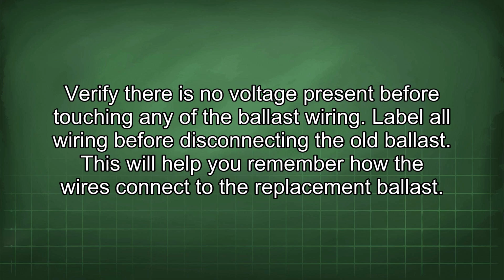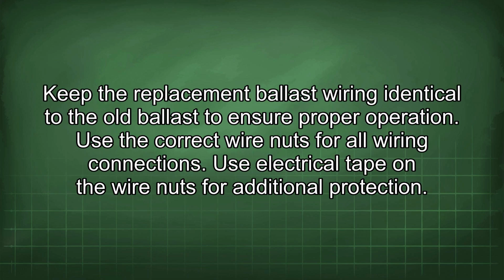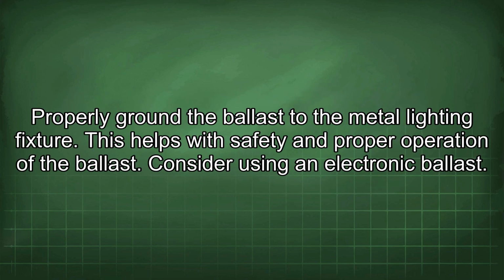Label all wiring before disconnecting the old ballast. This will help you remember how the wires connect to the replacement ballast. Keep the replacement ballast wiring identical to the old ballast to ensure proper operation. Use the correct wire nuts for all wiring connections. Use electrical tape on the wire nuts for additional protection. Properly ground the ballast to the metal lighting fixture. This helps with safety and proper operation of the ballast.